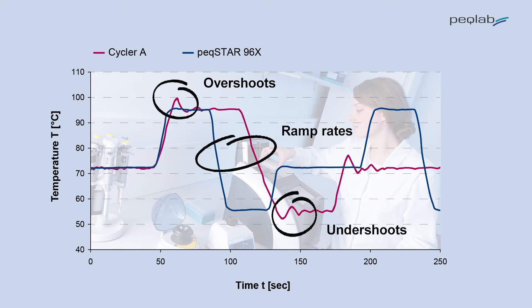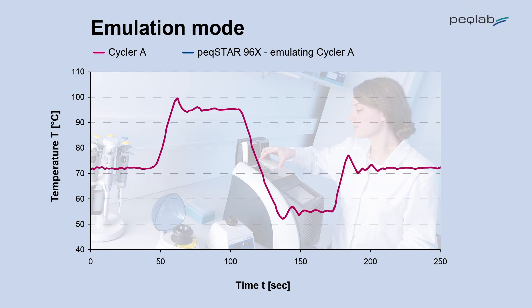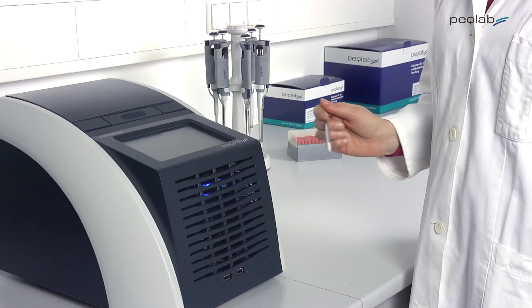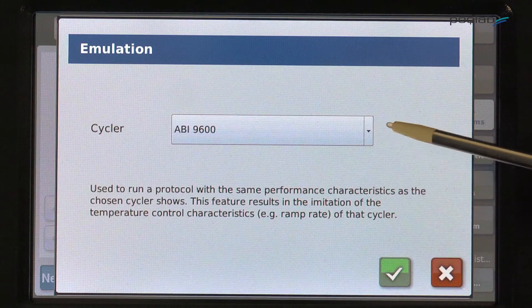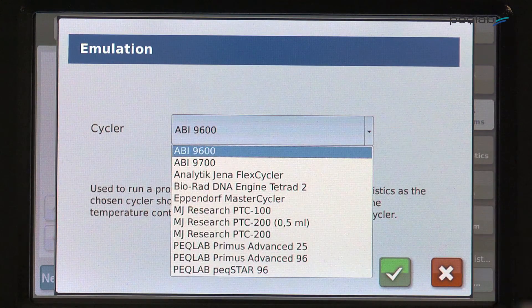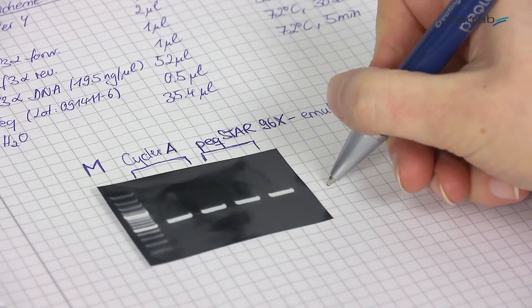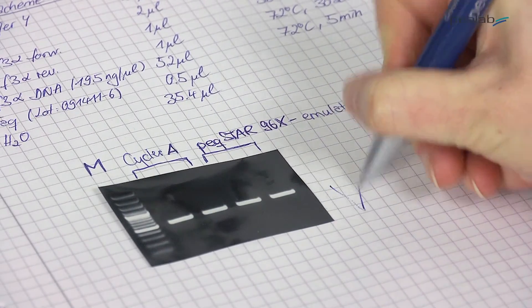With the peqSTAR range, we now give you the option to run in normal peqSTAR mode, or actually to emulate or copy the temperature profile of another type of cycler. Just choose another brand from the emulation mode to copy its performance, and by doing so, identical PCR results will be obtained.